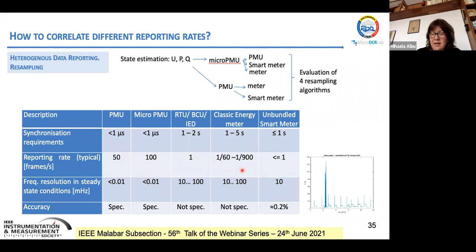Of course, we can think of various ways of combining, which means either decimation of the PMU high reporting rate measurements up to the 1 second smart metering provided measurements, or we can, let's say, artificially oversample the measurements provided by the smart meters in order to obtain rates similar to the PMUs. But this downsampling or oversampling can be done in various ways, and each way can inflate the associated measurement error differently. And here are some examples of how we can do this with the PMUs and the smart meters if we go to the 1 second reporting rate.